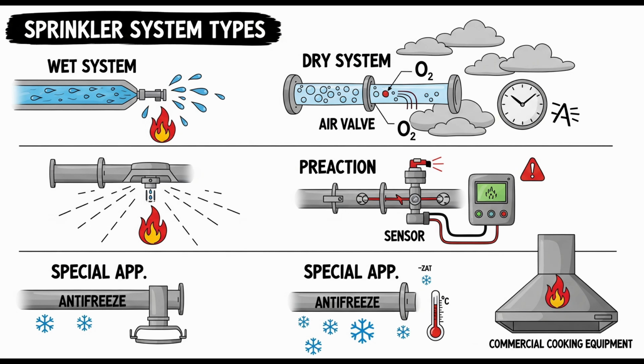That's a significant advantage. So if you want this benefit, how do you supply the nitrogen? If nitrogen is used specifically for this purpose, to justify using that higher C value in calculations, the supply must come from a listed nitrogen generator that is permanently installed. So not just bringing in bottles of nitrogen periodically, it needs an on-site generator. Correct. For this specific application aiming for the hydraulic benefit, it requires a listed generator. This generator must be capable of supplying and maintaining a minimum of 98% nitrogen concentration throughout the entire sprinkler system piping. High purity is important.